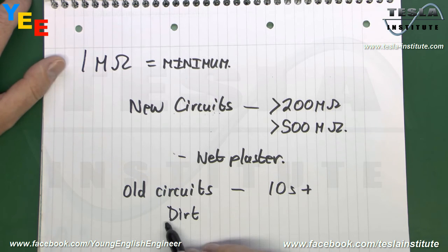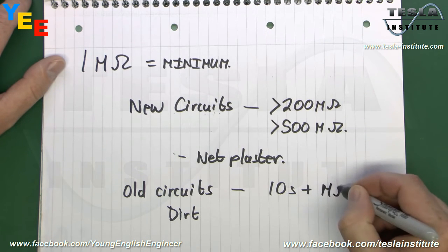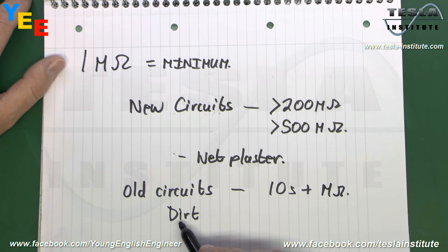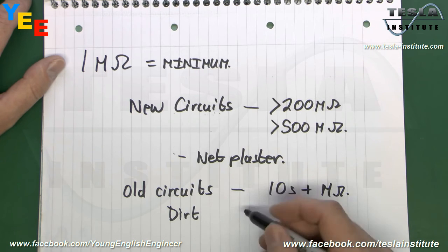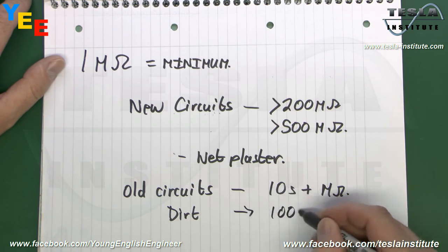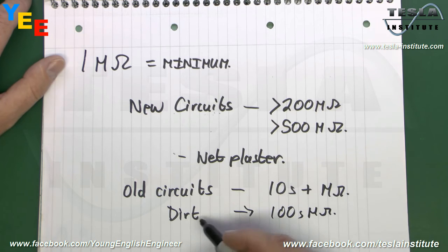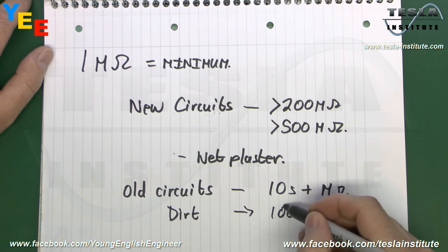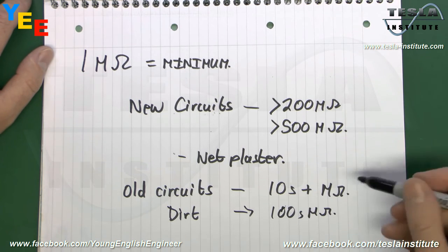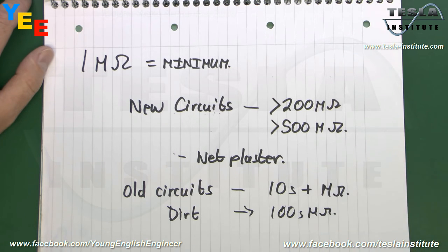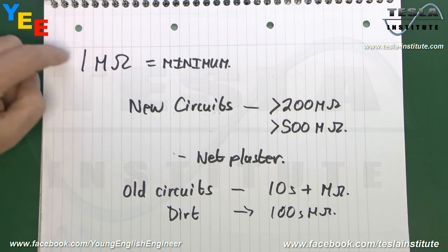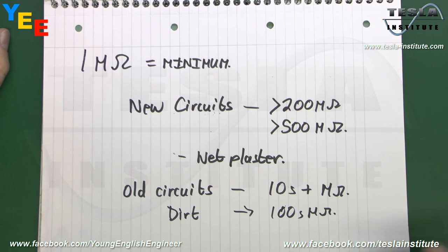It's quite often the case as well that if you find one in the low tens of megohms, and you go around all the sockets, take them off, clean all the wires and remove all the disgusting black grime and put them back together again, you can suddenly find it's now in the hundreds of megohms, simply from cleaning a bit of dirt away, as dirt in houses tends to be rather oily and does conduct a little bit of electricity. But ultimately, 10 is still acceptable, though this 10 plus range is really much better than the 1. Bearing in mind, if you've got one at, say, 1.2, that could easily drop below 1 five minutes after you've left the building.